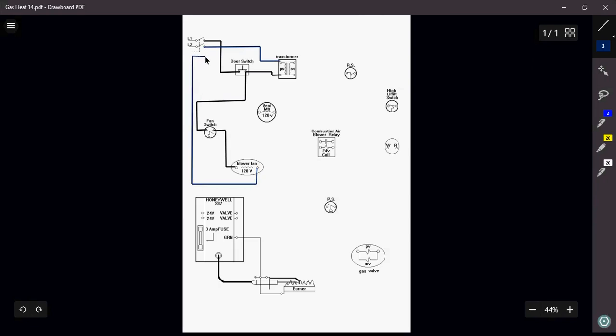Now, when we're looking at diagrams like this, okay, this is sort of like a pictorial diagram. It's not necessarily a ladder diagram. It's a pictorial. Because when we look at any piece of equipment, nothing in wiring is going to be all nice and neat, and you're going to be able to easily identify where things go. You're going to have to look at any wiring diagram, whether it's a pictorial or a ladder, and you're going to have to, unfortunately, get down on your knees, sit on your service bucket, whatever it is, sit on your butt, and physically pull the wires and look at the wiring diagram that goes with that furnace to see where these things are, to see if it is wired correctly.